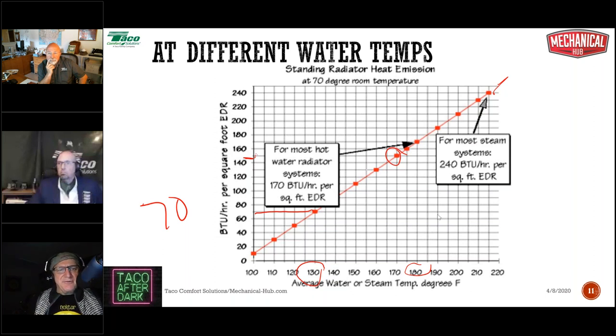If you had a big old cast iron radiator, a lot of people rehab these older homes and they love the cast iron radiators, but they button up the envelopes, and the heat load goes down and they want to reuse these radiators. Now with a little bit of math, and if you know the heat load and you know what the EDR is, you may be able to say, hey, I don't have to run 180 degree water here. I can run 130 degree water here or 140 degree water here. It's just a matter of you can't make that decision without doing the math. You have to do the math to know what you can do and what you can't do.